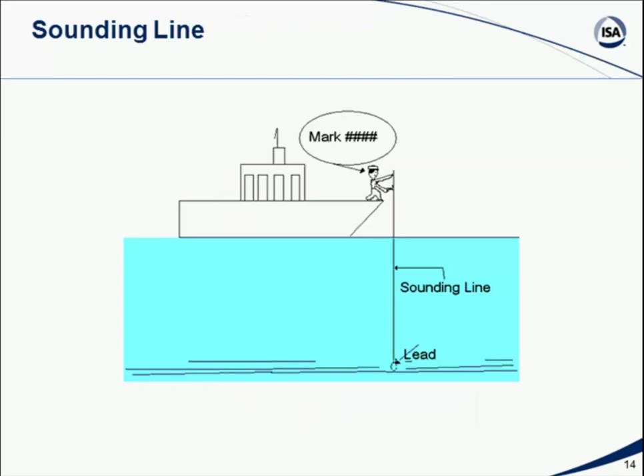If any of you are avid readers of Mark Twain, then you might have figured out eventually where the name comes from. And "mark twain" is actually something that was said. It was a way that if someone was on a riverboat and you're trying to determine the level in fathoms of the water to make sure that the boat doesn't run aground, then you'd have a person out at the bow with a sounding line, which is just a long string with a lead weight at the bottom, and they would throw it over and try and find out how far down before the weight hit bottom, and then they'd yell out "Mark Twain." So it was, again, essentially a dipstick, but instead of a solid thing, we're using a strip of line that, again, becomes wetted by the water or fluid. So, again, we've got a way of making a manual measurement.